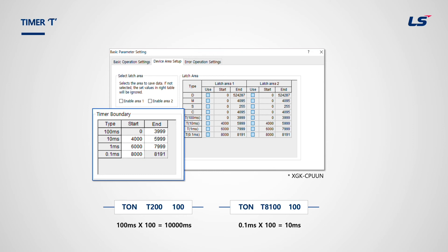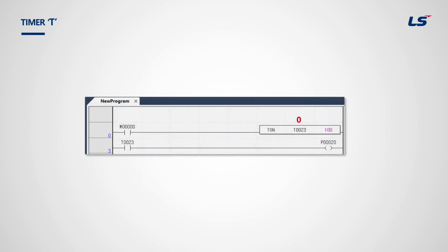For example, T8100 lies between T8000 and T8191 on the last row, so that timer has a value of 0.1 milliseconds. In the ladder program example, when M0 bit is on, the timer-on function starts. T23 timer has a value of 100 milliseconds, and because the function is set as 100, it means 10 seconds. After 10 seconds, T23 will reach 100, turning the T23 bit on, and therefore P20 output is on.